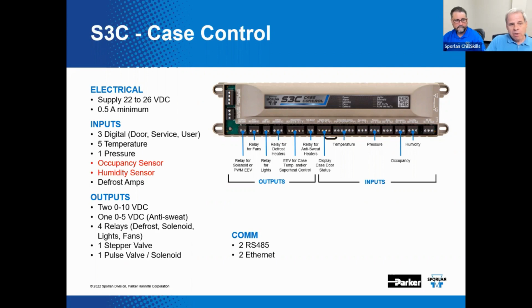Digital inputs, well, you can have dry contact or open collector connections. There's negative reference to be supplied by the case control only. There is an option for an occupancy sensor. We got door switches, service switches. It's user configurable, and we've got analog inputs as well. John, can you tell us a little bit about that? So there are up to 5 temperature inputs on there. The S3C can handle 2K, 3K, and 10K thermistors. So that's selectable in the software. Also, auxiliary temperature inputs configurable via software, and also current transformer or CT inputs, CT outputs, 0 to 5 volts DC, measuring from 0 to 50 amps.